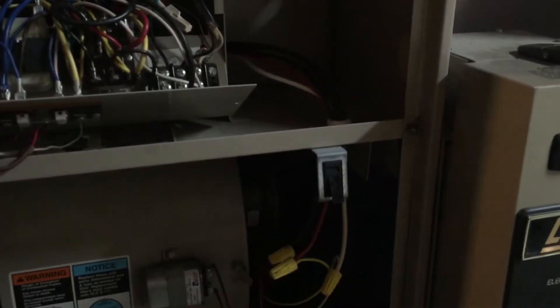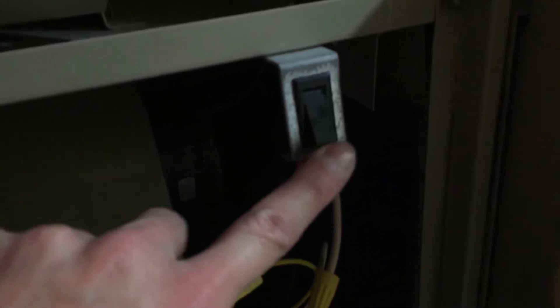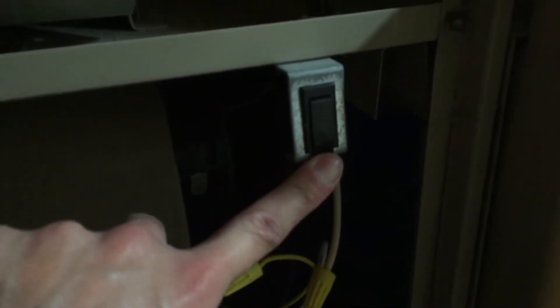I was looking around on it and as I took these door panels off, I've got this little switch here on the door that covers this blower motor. Closes the switch. So when the switch is out, nothing switches in. I got 120 volts through this system so I knew the switch was working.